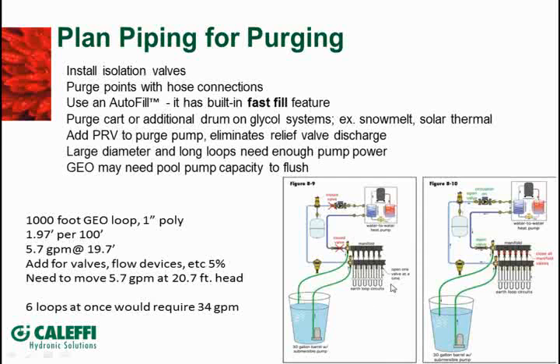So in this application, if you've got a geo system that's manifolded like this, you've got the ability to purge the air out of these loop fields without even having to go in the mechanical room and worry about purging all this line capacity out too. So you're breaking it into small bite-sized pieces. So go out, purge this out first, or if this is a mechanical room location, purge it out here, shut it off, and now you can purge out this loop here.